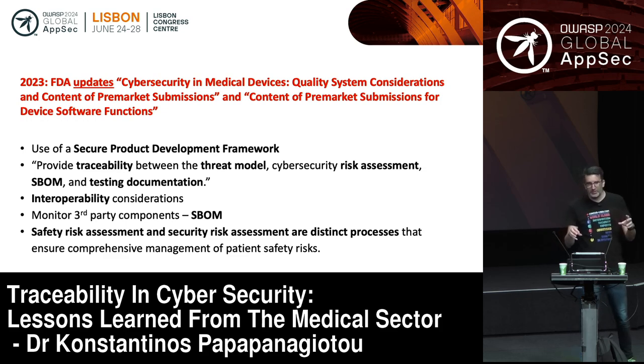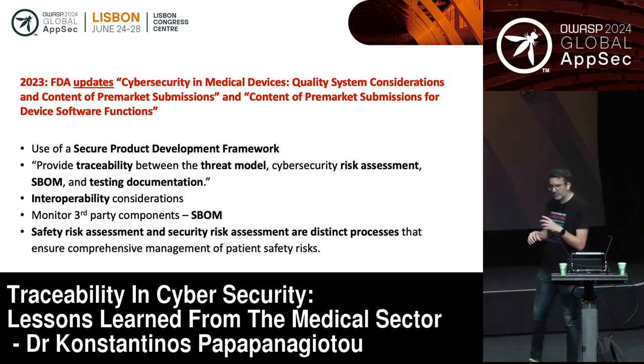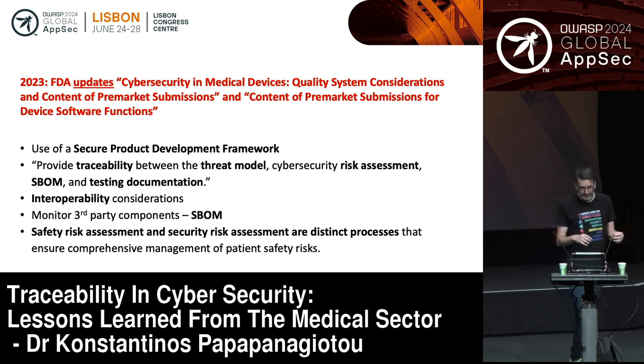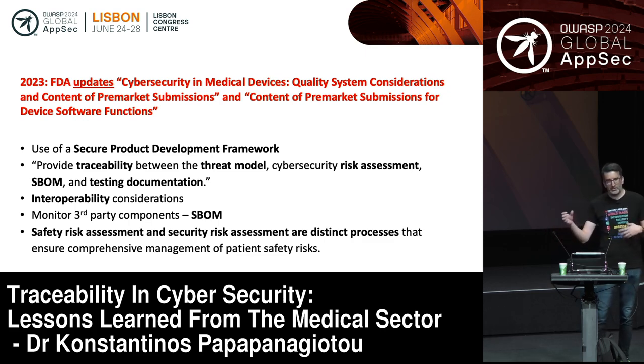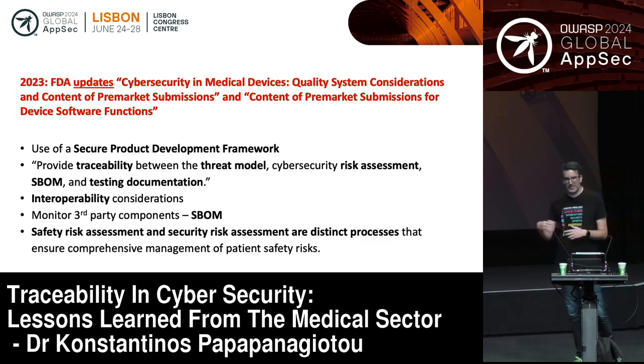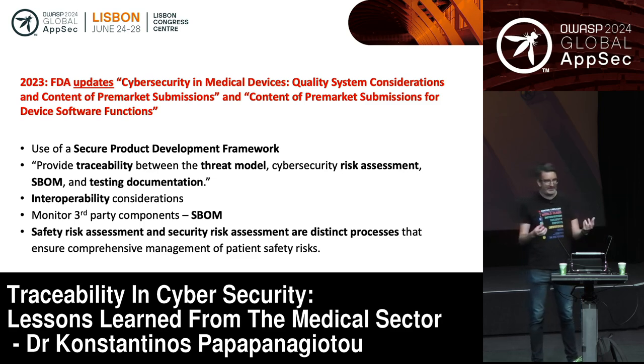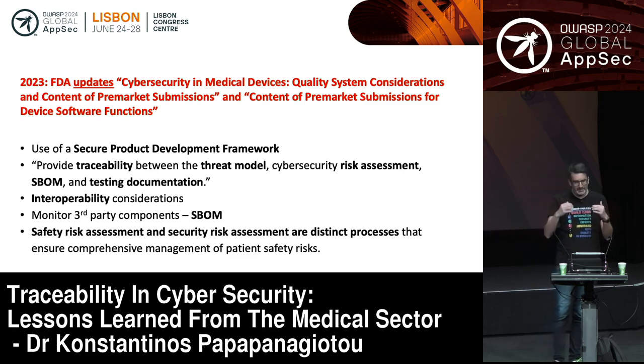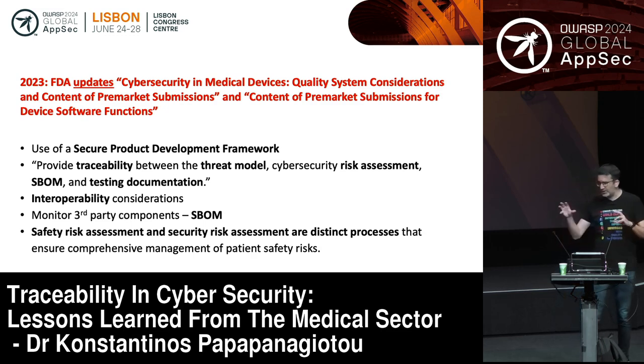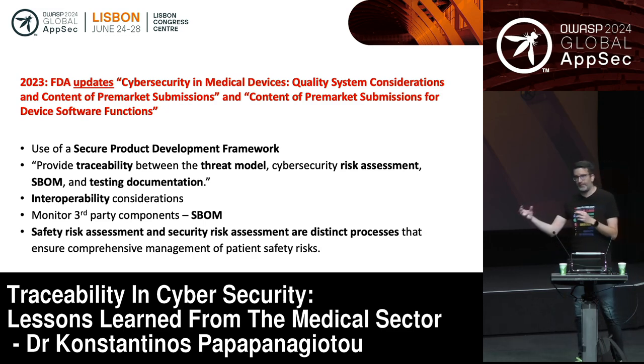These are actually two different processes. When you do safety risk assessment on a medical device, you're trying to understand what might go wrong and harm the patient. When you do security risk assessment, you're trying to find vulnerabilities that introduce a security risk. Now, these may seem like two distinct activities, but FDA comes and says that these are not actually completely distinct. One might be affecting the other.